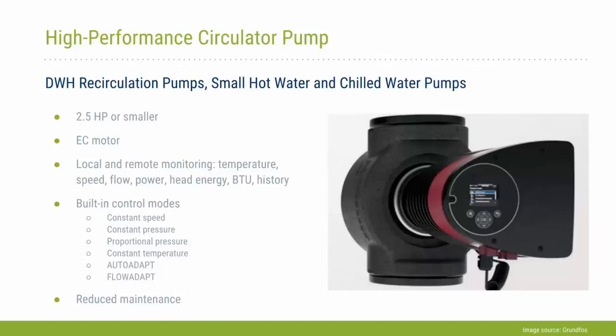This particular vendor has a number of control modes that are integrated into the pump. You'll see there's constant speed, constant pressure, proportional pressure, auto adapt, flow adapt. The one that is used for domestic hot water recirculation pumps is the constant temperature mode, where the pump has an internal temperature sensor in it, and you typically set that return water temperature set point to about 10 degrees Fahrenheit below the domestic hot water tank set point. And then the pump will essentially ramp up and down to meet that set point temperature. I would say some of the other control modes in here, like auto adapt and flow adapt, are more geared towards air handling unit applications.